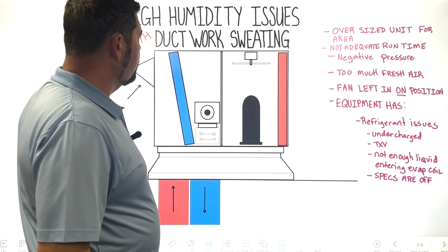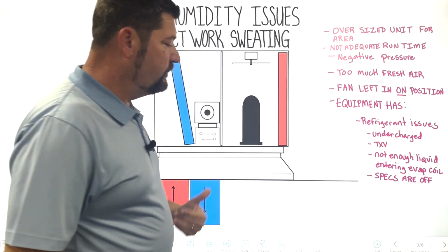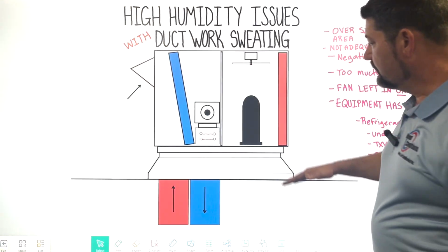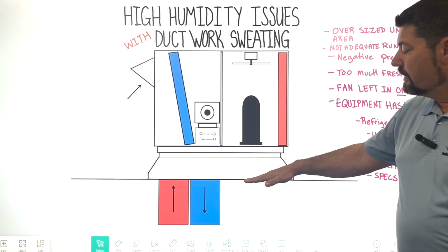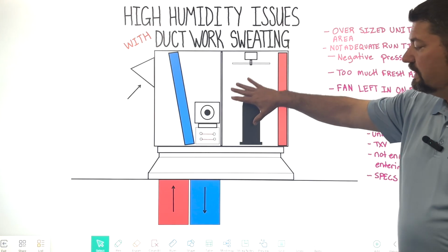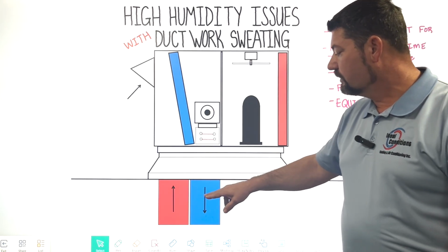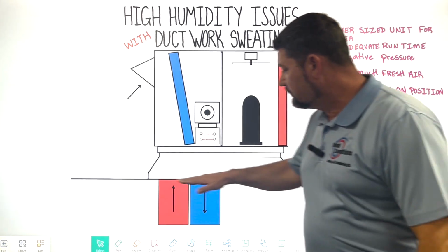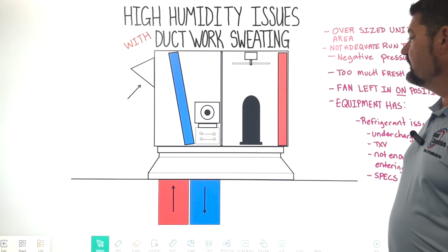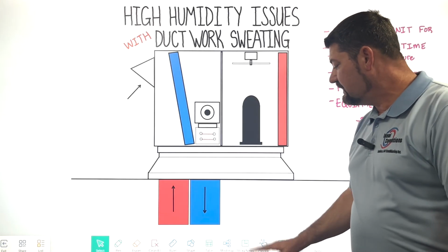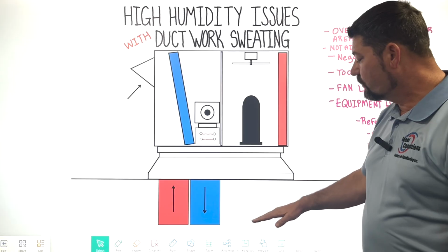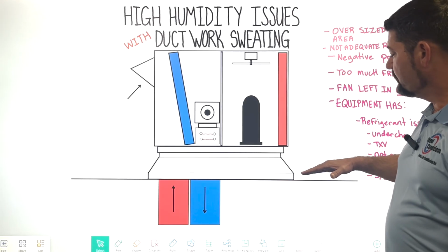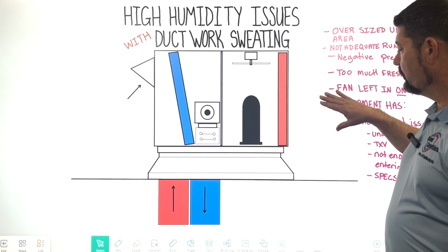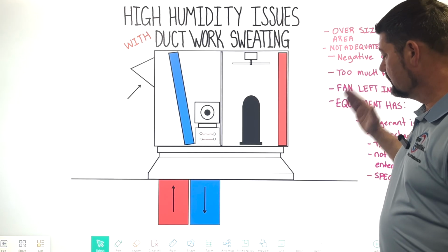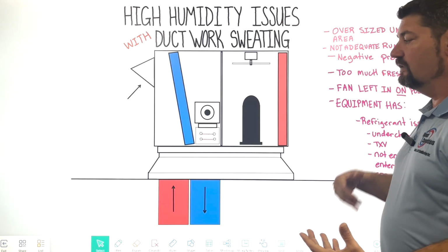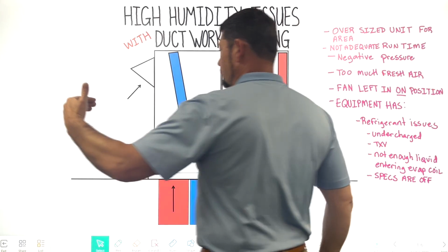Now, with regard to ductwork sweating, I'm going to go to another page to better explain that. That kind of talks about what happens below the roof deck. All right, so we got the RTU, we have the curb, we have the return, and we have the supply plenum, and then this bottom line here, this would be the roof deck, right? And so we have conditioned space down here, we have the temperature above the grid and below the roof deck, and then we have the temperatures above the roof deck, which are both ambient and with the heat index, because that roof is just absorbing more heat than the surrounding air that's right in this area.